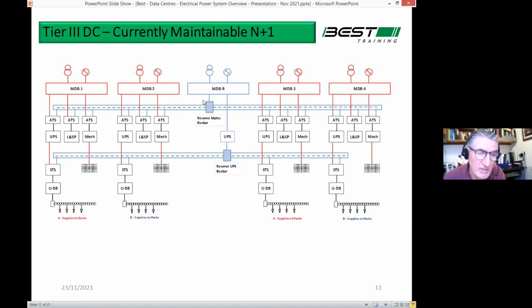Okay. Now, when we get further down, you will see you come through the UPS. So the UPS, which we'll talk about in a few minutes, is your battery backup system that converts battery power into AC power, and it's a no-break supply arrangement. And that provides power down to your UPS distribution boards and out to the load. So you see I'm showing A supplies to the rack, then B supplies to the rack, typically. So it means that every rack has an A supply going into it and a B supply. And then every server connects to an A and a B supply. So you're bringing that resilience all the way down from the HV network right down to the back of the rack. That has a dual pathway to every single server. If one supply fails, it automatically picks up the supply off the other one.